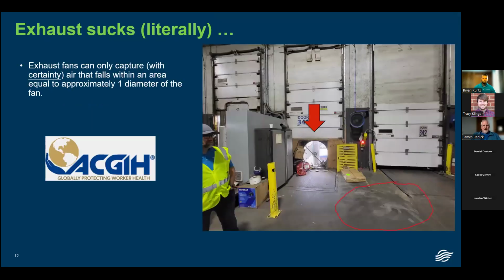Okay. Truly, exhaust sucks, literally. That image there, I've got an arrow pointing at an exhaust fan. This is a building where they were trying to manage dirt. This is an area where there's a process going on. They're crushing products, or crushing waste product, packaging, etc. And they put an exhaust fan there. That exhaust fan is running and moving a decent amount of air, probably 10 to 15,000 CFM.